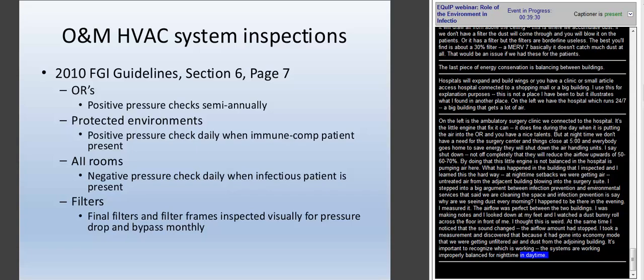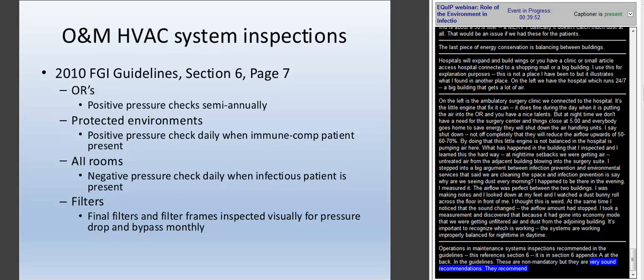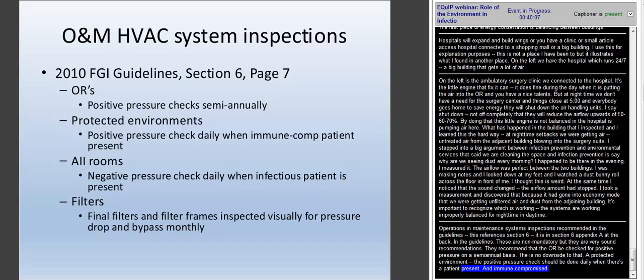So, operations and maintenance systems inspections that are recommended in the guidelines. Now, this references Section 6. Yes, it's in Section 6, but it is in Appendix A at the very back of the guidelines in the 2010 and 2014 guidelines. And these are non-mandatory recommendations, but they are very sound recommendations. They recommend that the ORs be checked for positive pressure on a semi-annual basis. There's no downside to doing that. That the protected environments, that the positive pressure check be done daily when there's a patient present, an immune-compromised patient present. Nothing about that does not make sense. It's a great recommendation. For AII rooms, negative pressure checks on a daily basis when infection patients are present.